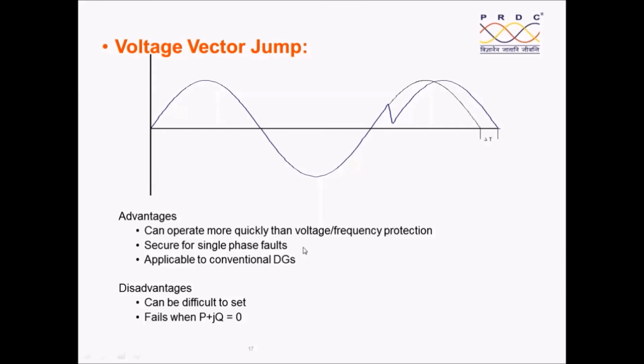And it should not operate for a single phase fault, because whenever there is a single phase fault in the grid, or a three phase fault far away from your captive power plant bus, it may so happen that this vector shift angle will be less. Therefore, I should not trip. Normally, the setting for this is somewhere around 5 to 7 degrees.